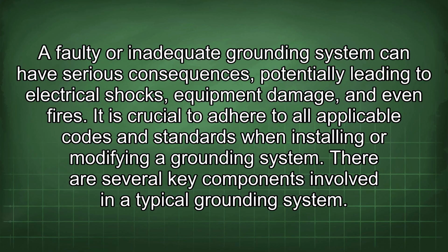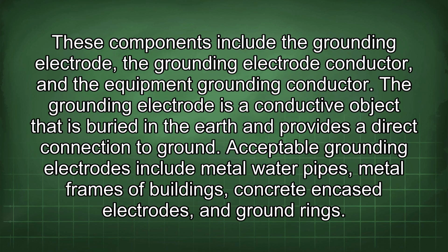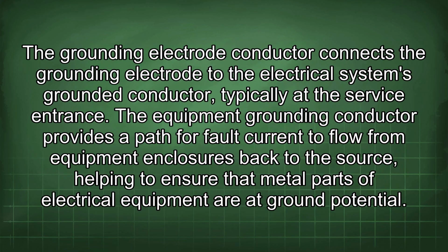There are several key components involved in a typical grounding system. These components include the grounding electrode, the grounding electrode conductor, and the equipment grounding conductor. The grounding electrode is a conductive object that is buried in the earth and provides a direct connection to ground. Acceptable grounding electrodes include metal water pipes, metal frames of buildings, concrete encased electrodes, and ground rings. The grounding electrode conductor connects the grounding electrode to the electrical system's grounded conductor, typically at the service entrance. The equipment grounding conductor provides a path for fault current to flow from equipment enclosures back to the source, helping to ensure that metal parts of electrical equipment are at ground potential.